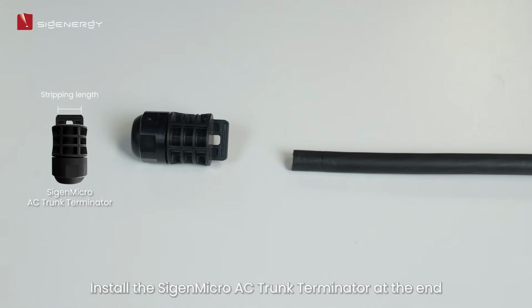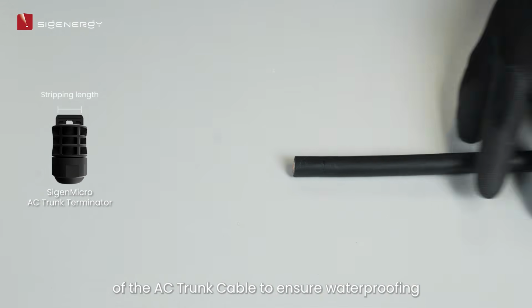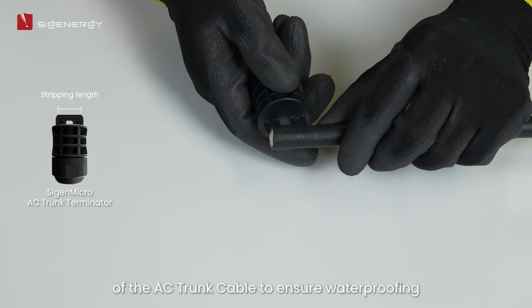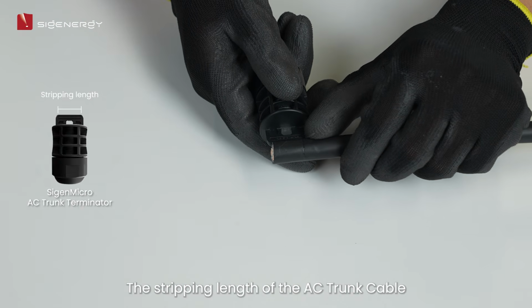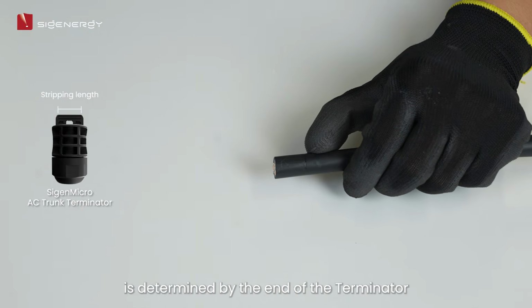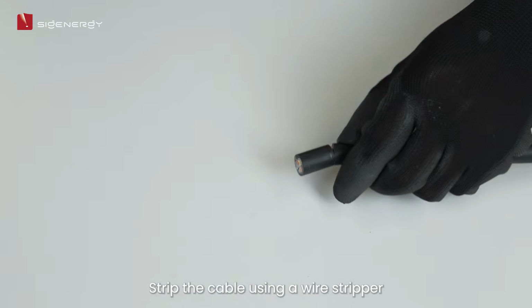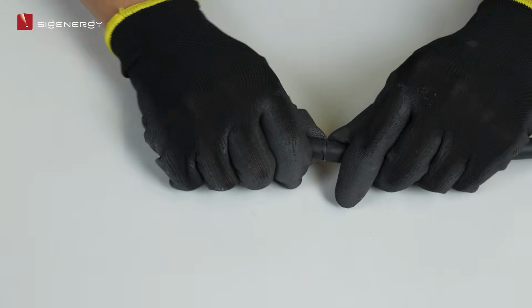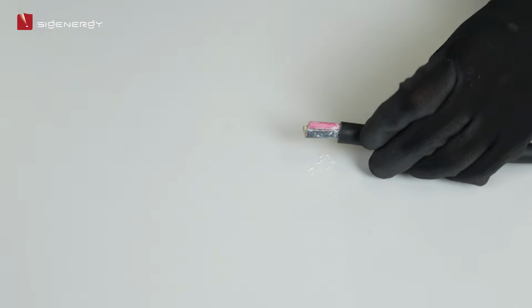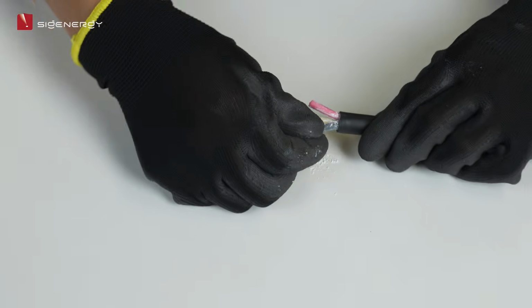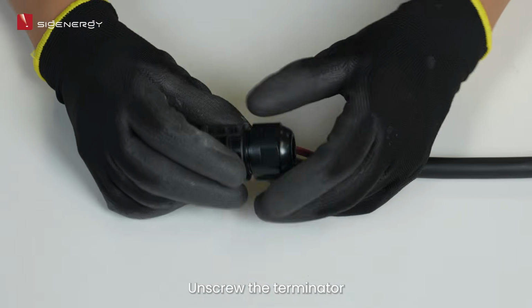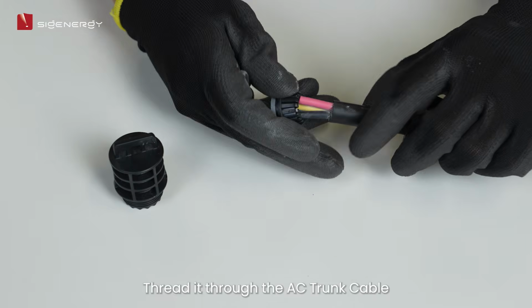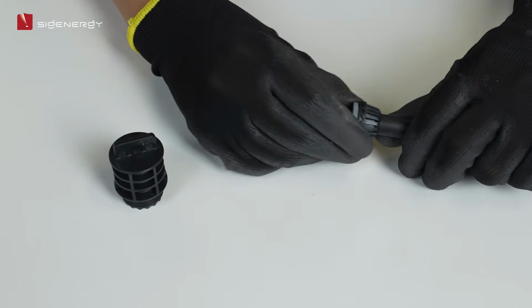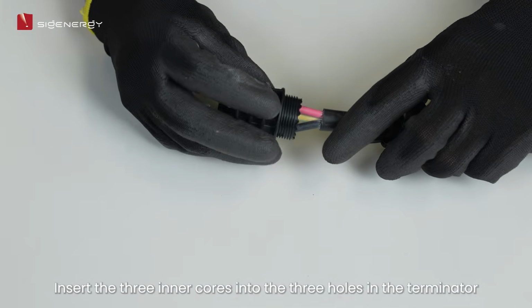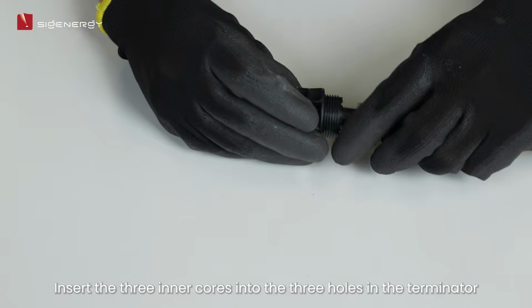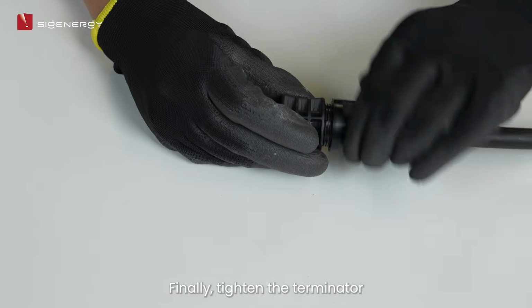Install the SigenMicro AC trunk terminator at the end of the AC trunk cable to ensure waterproofing. The stripping length of the AC trunk cable is determined by the end of the terminator. Strip the cable using a wire stripper. Unscrew the terminator. Thread it through the AC trunk cable. Insert the 3 inner cores into the 3 holes in the terminator. Finally, tighten the terminator.